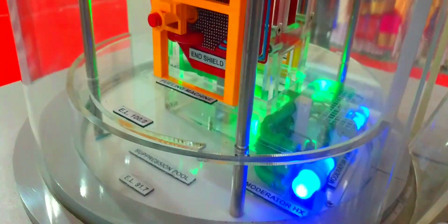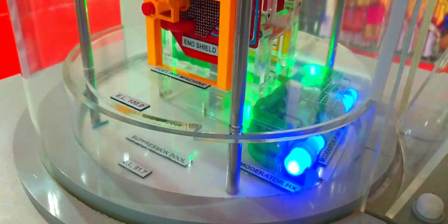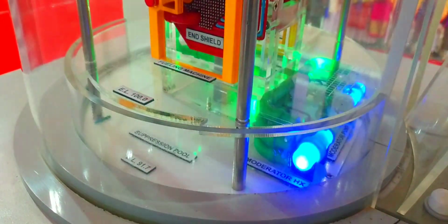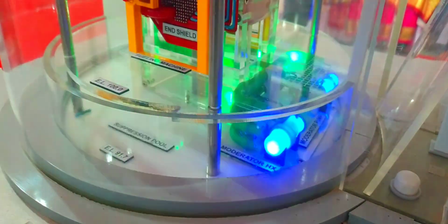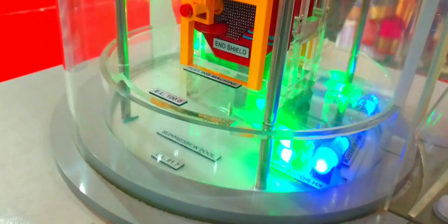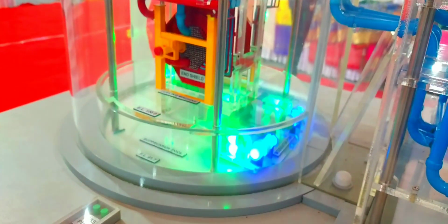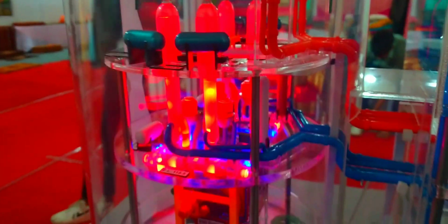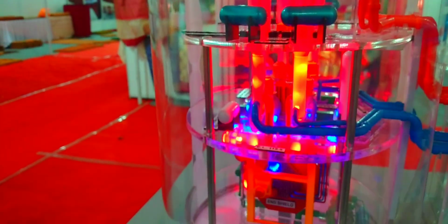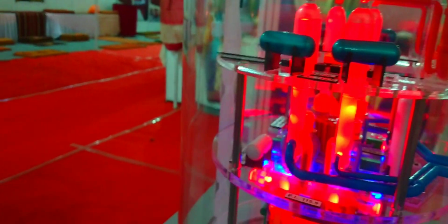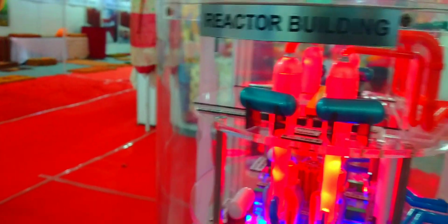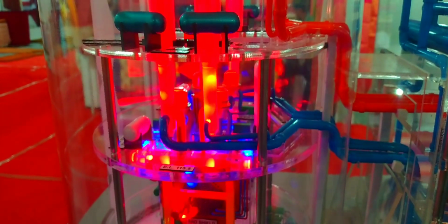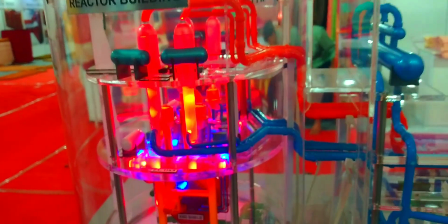This heavy water is required to control and slow down the fission reaction. The heavy water, which has 2 atoms of deuterium, has a quality of not absorbing neutrons in large quantities. This process of moderation of neutrons is essential for the chain reaction process. The hot coolant heavy water flows out of the calandria and is transferred to steam generators. The 4 steam generators and pumps are shown above the calandria in silver grey and green colors respectively.